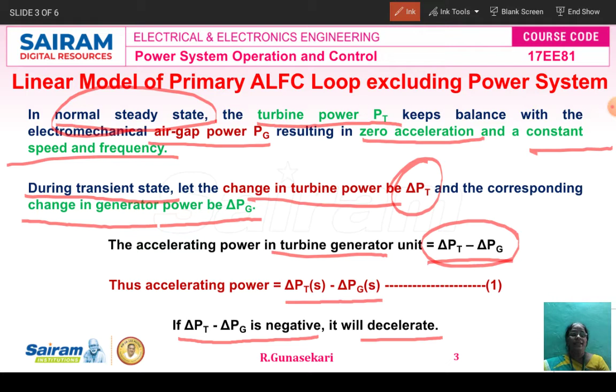The turbine increment del PT depends on the valve power increment del PV, that is the hydraulic valve actuator, and the characteristics of the turbine. If it is a hydro power plant, the water turbine has some characteristics; if it is a steam turbine, steam characteristics. Different types of turbines have different characteristics: steam turbine, water turbine, Kaplan turbine, Francis turbine, propeller turbine, Pelton wheel turbine. Every turbine has different characteristics. So based on the characteristics of the turbine, valve power increment del PV gives the turbine power increment del PT.